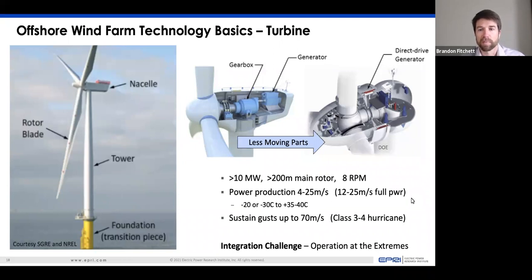The temperature ranges have been unchanged over the last 30, 40 years. Usually that range is somewhere in the neighborhood of minus 20 or minus 30 Celsius up to sometimes 35 or up to 40 Celsius for hot weather wind turbines. Just pointing out, the potential operation up to 30 meters per second, that's a halfway decent tropical storm where you could still be operating and producing power through it. And that may be needed, especially in the Northeast. Even in the winter, where nor'easter storms come through, you can definitely get these kind of 50, 60 mile an hour winds offshore, and being able to produce power and support the grid on those cold days onshore is extremely valuable.